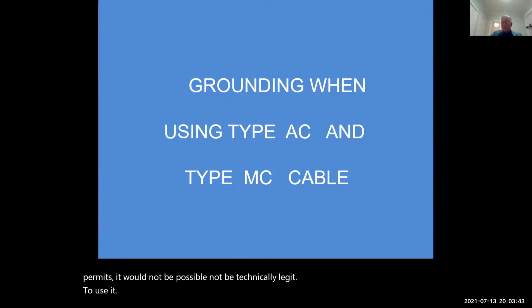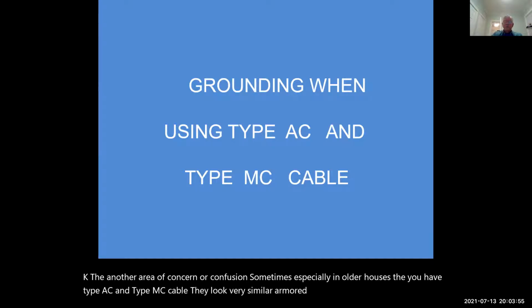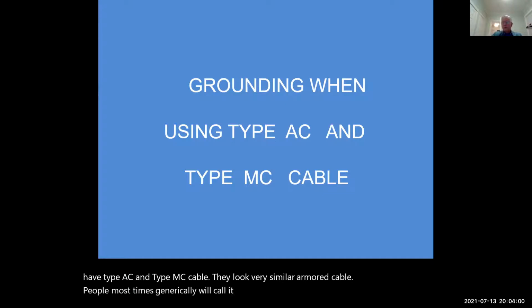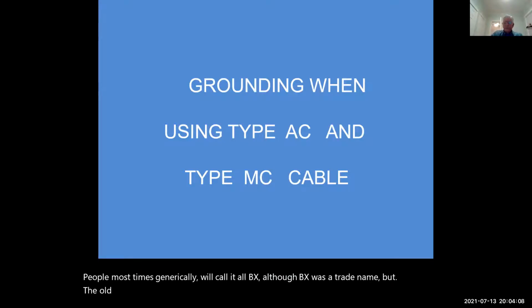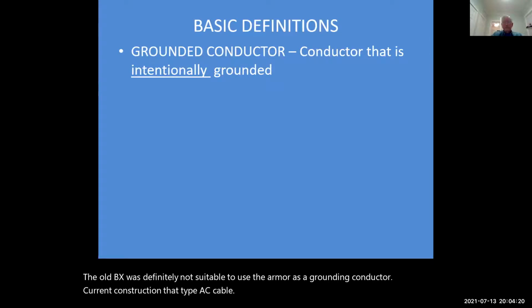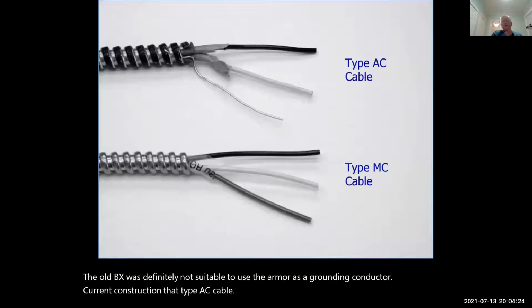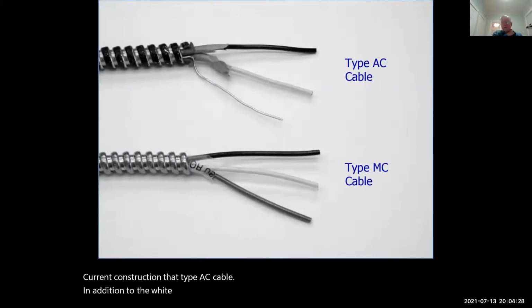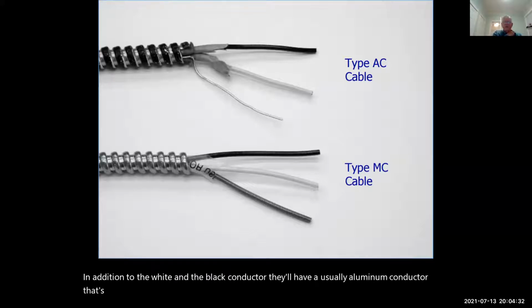Okay, another area of concern or confusion sometimes, especially in older houses: you have type AC and type MC cable. They look very similar, armored cable. People most times generically will call it all BX, although BX was a trade name. But the old BX was definitely not suitable to use the armor as a grounding conductor. Current construction type AC cable, in addition to the white and the black conductor, will usually have an aluminum conductor that's basically like a drain wire that bonds across the convolutions of the armor. And the armor then can be used as your equipment ground conductor.